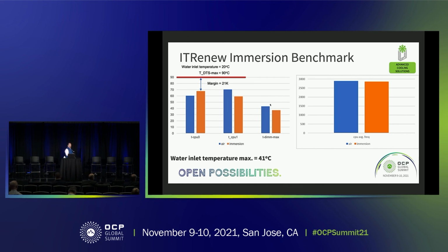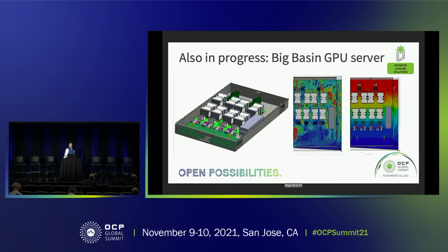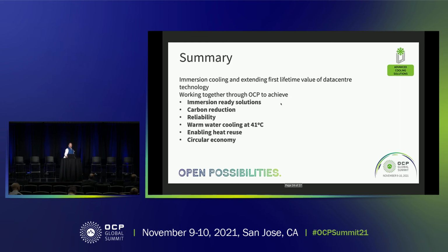So it's a good indication of performance, and we believe we can close the gap between measurements and the full potential from the CFD results by optimizing the heatsink, which was indeed designed for air cooling. We can make improvements for that heatsink by looking how it can be optimized for immersion. So all in all, a great outcome. We are working also on a big basin solution based on the same immersion, natural convection approach to cooling. So more news to follow on big basin and other servers.